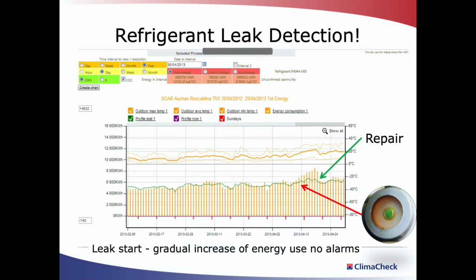Refrigerant leak detection is another capability whereby the system is looking at the performance of the machine in relation to ambient conditions, and once this starts to go out of the expected norm due to a refrigerant leak in this case, ClimaCheck can send alarms to a number of recipients, up to 8 maximum, to advise them that something is wrong with this system. You can then look at the system performance and decide whether or not it needs attention, and in this case refrigerant leakage, which has been shown up by excess superheat and limited subcooling, can then be repaired, and you can see the improvement in performance after this repair.